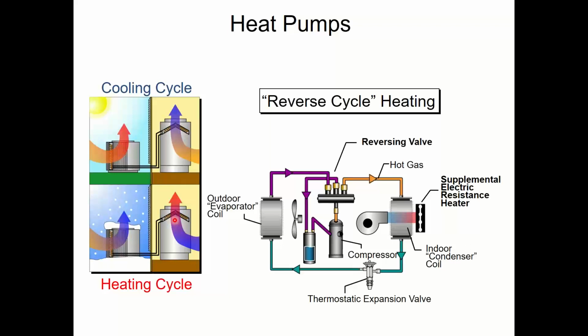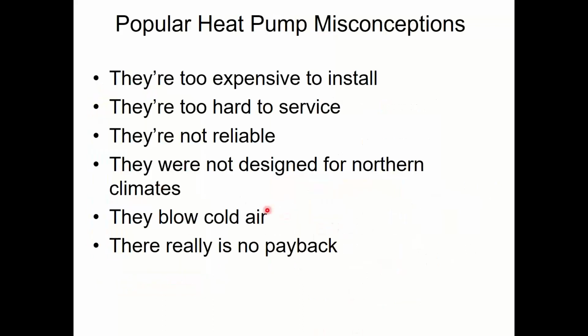What we do as the heat pump produces less heat, we sometimes increase the outdoor fan speed to try to grab as many BTUs as possible while decreasing the indoor fan speed in order to increase the temperature. I won't get any more BTUs doing that, but I can increase the temperature. The cold blow problem is largely solved.